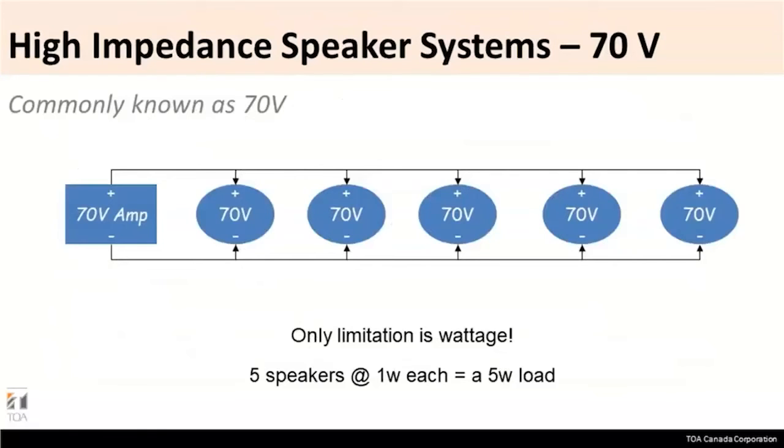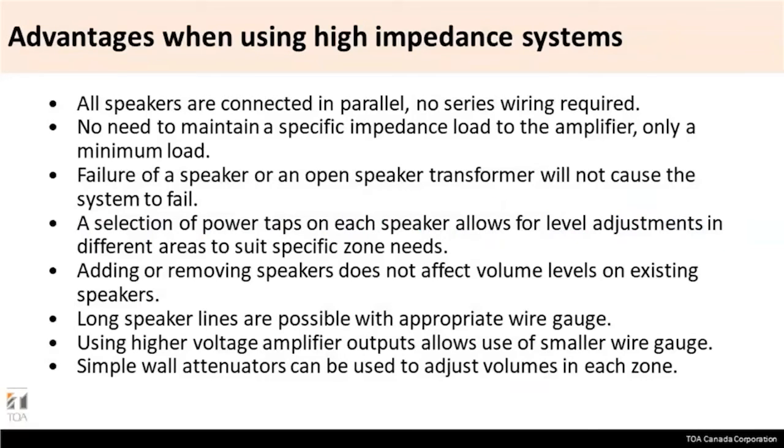In this example, there are five speakers. Let's say speaker number three goes bad for whatever reason, the system will not fail. You will still have announcement from speakers number one, two, four, and five. So it doesn't completely shut down the system. So point number three, failure of a speaker or an open speaker transformer will not cause the system to fail. It's very essential, because otherwise the maintenance cost will be way higher as compared to an 8-ohm system.